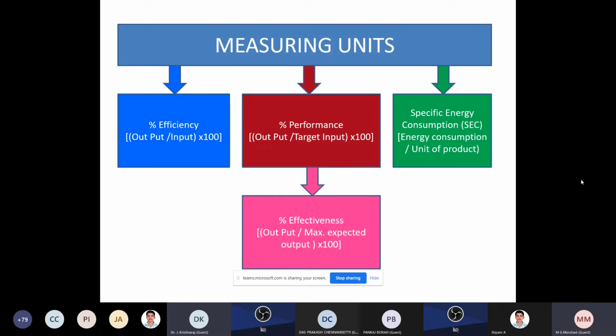Normally, we sometimes measure the performance on the basis of efficiency. We sometimes measure performance, specific energy consumption, and effectiveness. See, these are the four parameters we always try to establish during an energy audit: efficiency, performance, effectiveness, or specific power consumption, energy consumption. So these four are enough for establishing your energy audit. There is no big thing required. The design aspects, the LMTD and others, are basically used for design purposes, but design data is not very important here. Rather, what is very important is your operating condition with respect to the last data or the PG test data. Okay, is it clear?